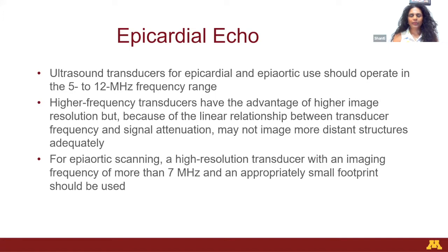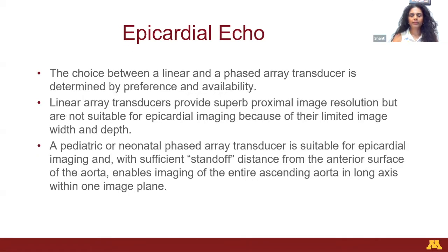So for epicardial echocardiogram, what type of transducers would you pick? Anything should operate between 5 to 12 megahertz frequency range. Higher frequency transducers have the advantage of higher image resolution, but because of the linear relationship between the transducer frequency and signal attenuation, may not image more distant structures adequately. For epi-aortic scanning, a high-resolution transducer with an imaging frequency of more than 7 megahertz and a small footprint should be used. The choice between linear and phased array transducer is determined by preference and availability.